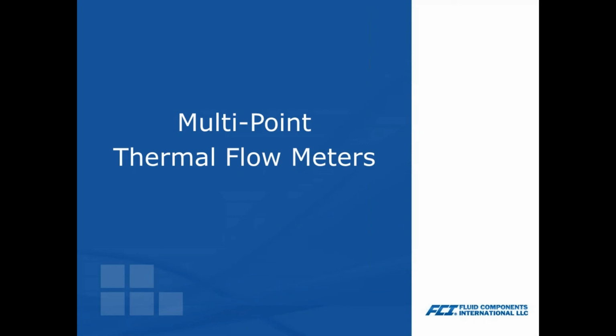Yeah. One of the big advantages of our thermal technology is this turn down capability, whether it be 100 to 1 on the basic units or 1,000 to 1 on the higher end units. You have that ability to have a much broader turn down. Your typical high end differential or multivariable transmitter is going to give you 8 to 1, 14 to 1 turn down, and it kind of limits you as to whether I catch the low end or the high end when I design my system. With that 100 to 1 turn down, we can get as low as a foot per second up to 100 feet per second as far as the velocity range goes.